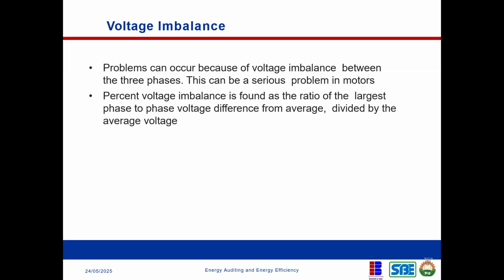Percentage voltage imbalance is found as a ratio. I'm talking about how we know when there's an imbalance in voltage, how do we calculate it, and what can be done. Percentage voltage imbalance is found as a ratio of the largest phase-to-phase voltage difference from the average, divided by the average voltage. Now I'm going to explain all of this with an example.